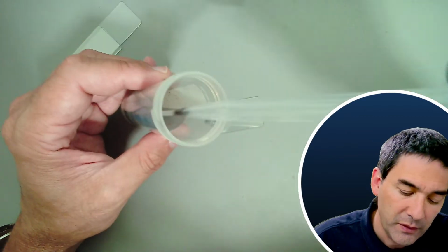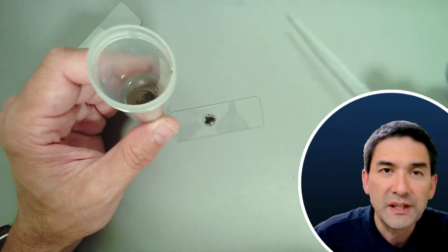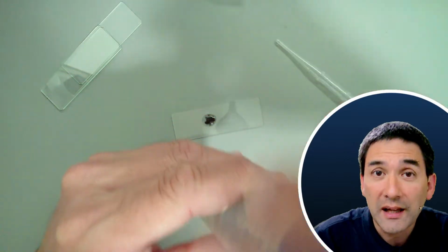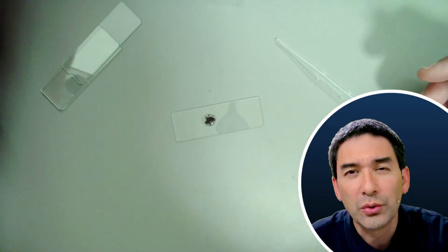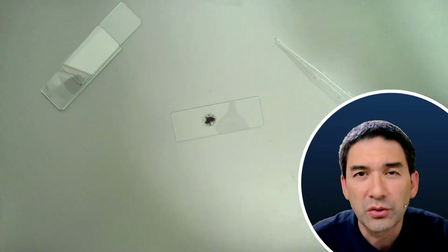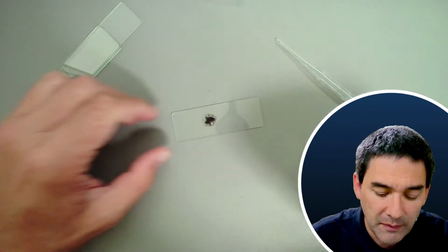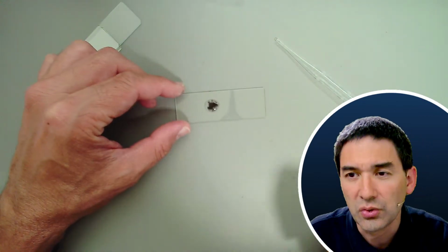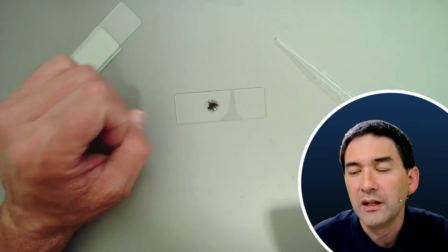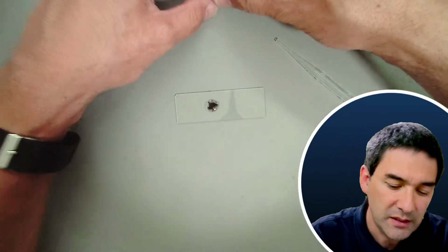Some companies sell compressed air in spray cans. These are used to remove dust from keyboards and so on, and you should not use those for optical surfaces because they contain some kind of solvent as well. So generally, alcohol only if there's really grease to be removed. Otherwise, I probably would not use alcohol because it's not necessary. Yeah, so let's do it like this here.